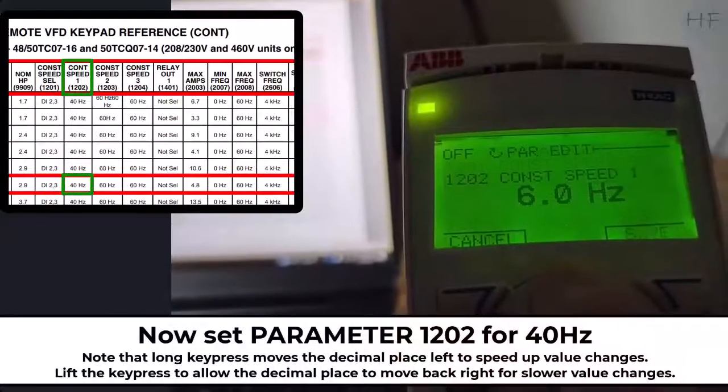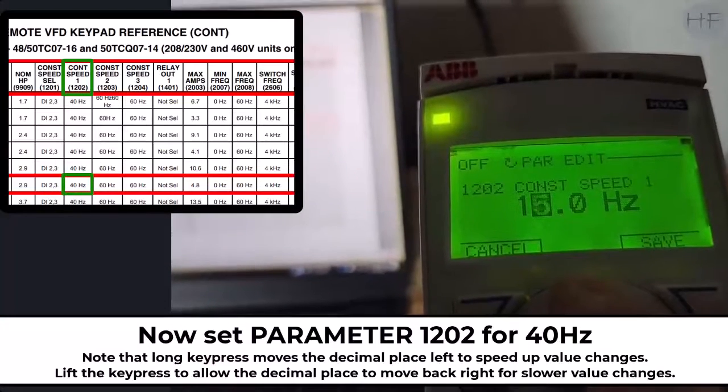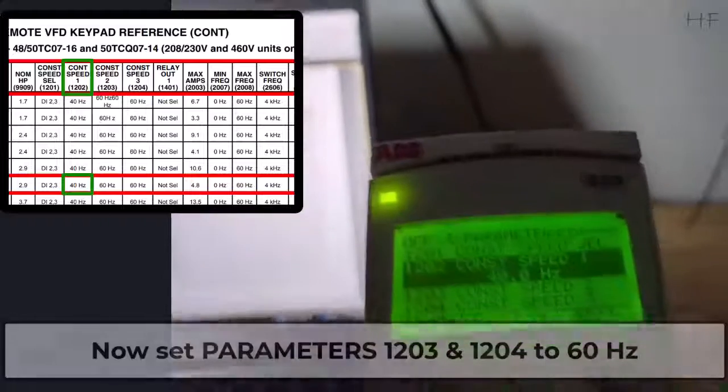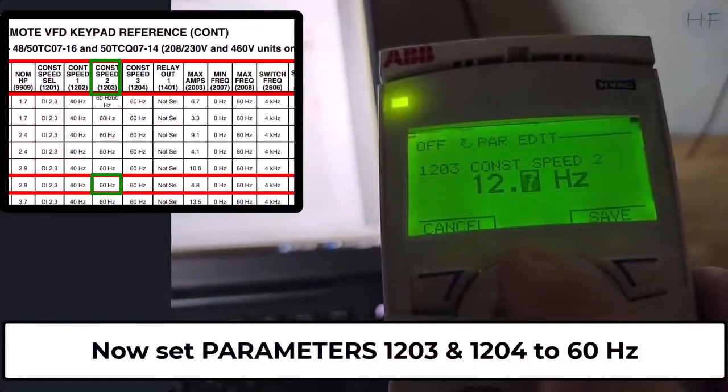Now set parameter 1202 for 40Hz. Note that a long key press will move the decimal to the left to speed up value changes. Now set parameter 1203 and parameter 1204 to 60Hz.